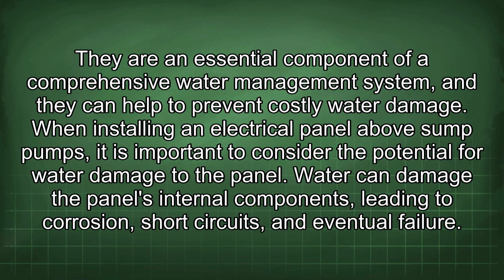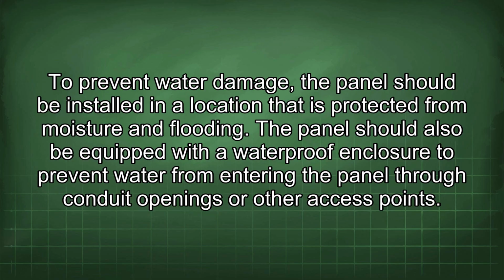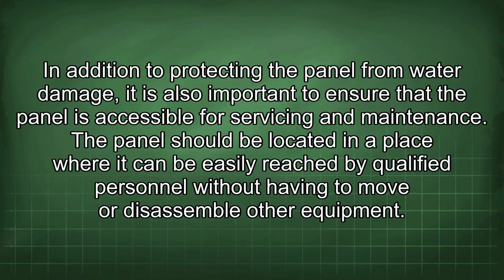When installing an electrical panel above sump pumps, it is important to consider the potential for water damage to the panel. Water can damage the panel's internal components, leading to corrosion, short circuits, and eventual failure. To prevent water damage, the panel should be installed in a location that is protected from moisture and flooding. The panel should also be equipped with a waterproof enclosure to prevent water from entering the panel through conduit openings or other access points. In addition to protecting the panel from water damage, it is also important to ensure that the panel is accessible for servicing and maintenance.